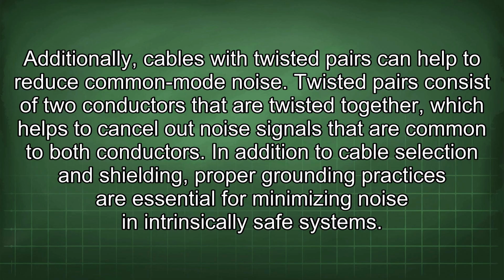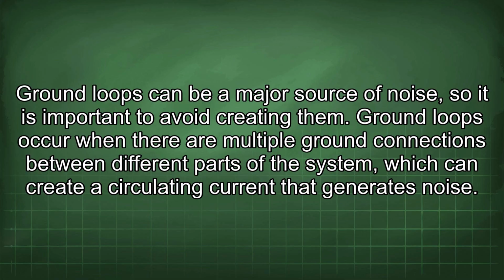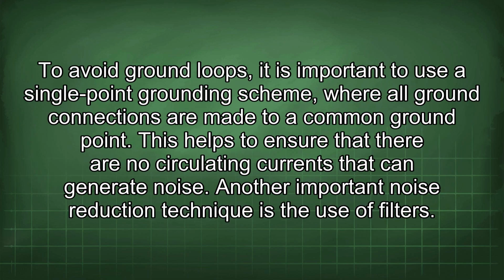In addition to cable selection and shielding, proper grounding practices are essential for minimizing noise in intrinsically safe systems. Ground loops can be a major source of noise, so it is important to avoid creating them. Ground loops occur when there are multiple ground connections between different parts of the system, which can create a circulating current that generates noise. To avoid ground loops, it is important to use a single point grounding scheme, where all ground connections are made to a common ground point. This helps to ensure that there are no circulating currents that can generate noise.